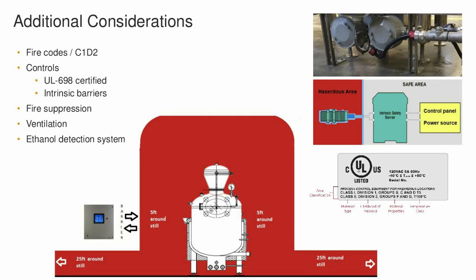But as they come out, the ethanol vapors are heavier than air. So they're going to drop down to the floor level and they'll start building up on the floor. That's why they call it the sombrero, because the bottom area is 25 feet away from the still. So that area, 3 foot off the ground, 25 foot around your still area, is considered the C1D2 area. So those are the problem spots. Those are the areas that if there is an issue and there is a spark, then that's going to cause the explosion. So what we have to do is make sure that that C1D2 area is treated properly.